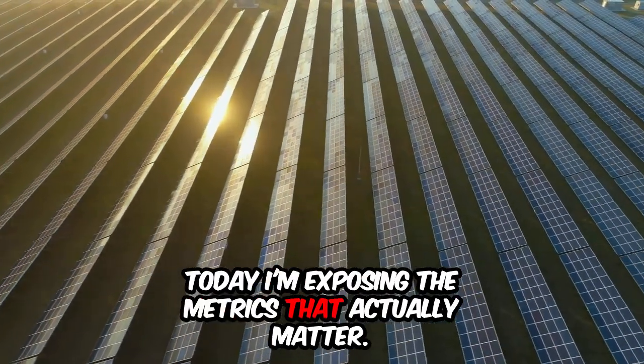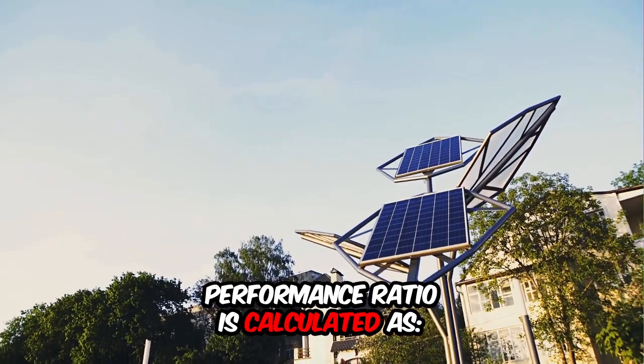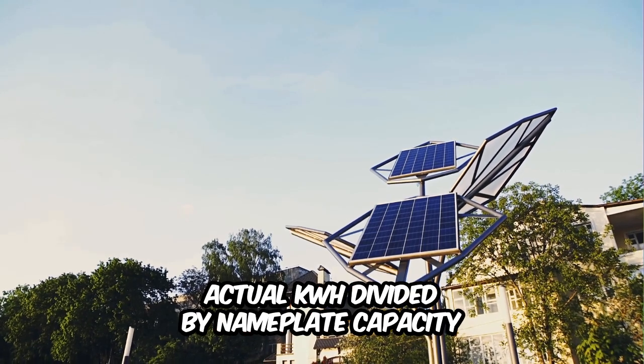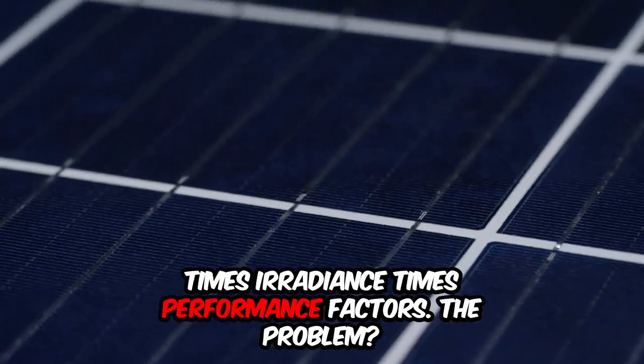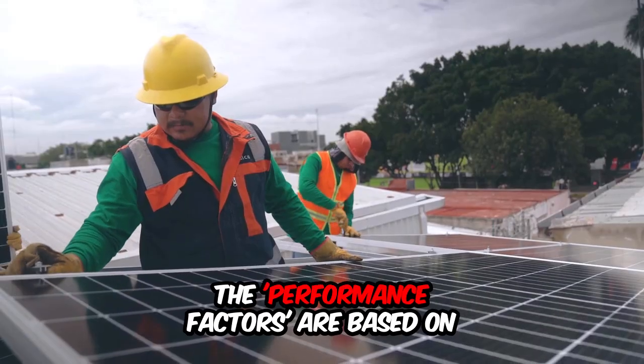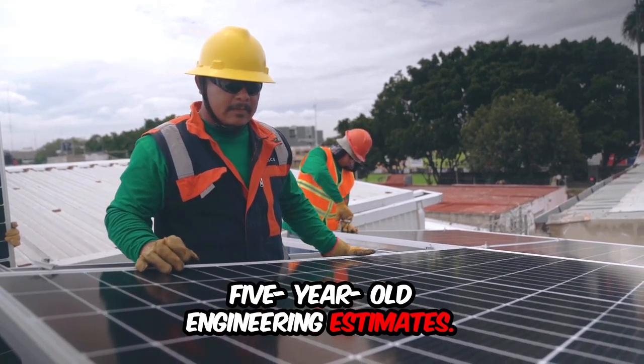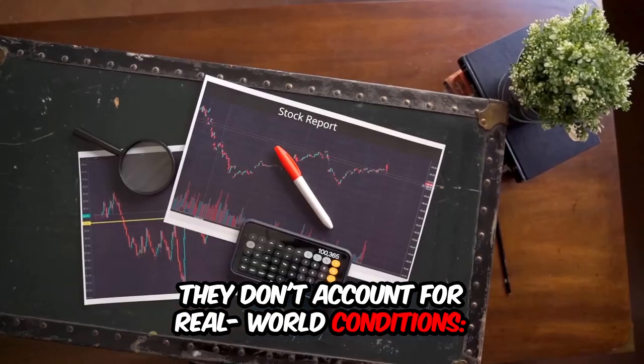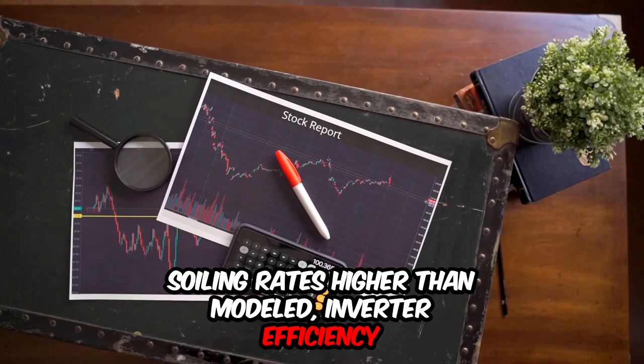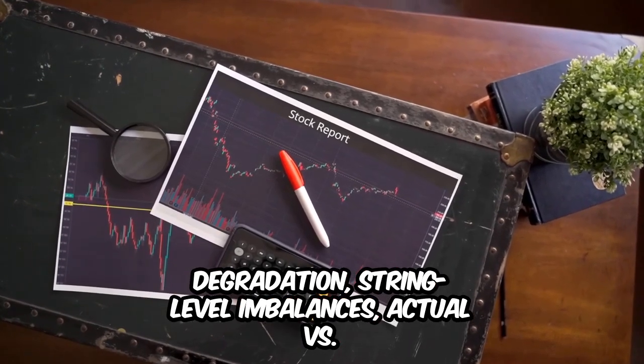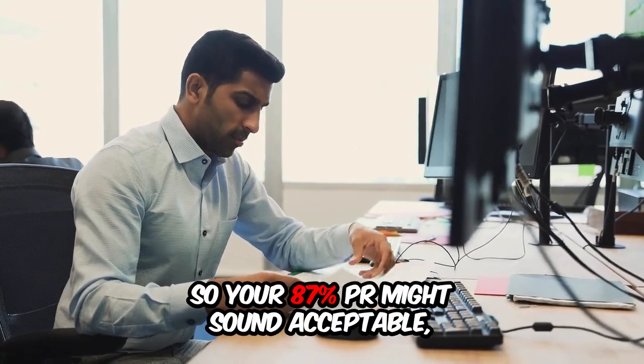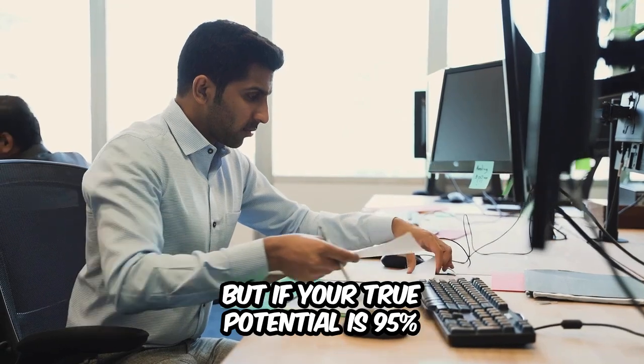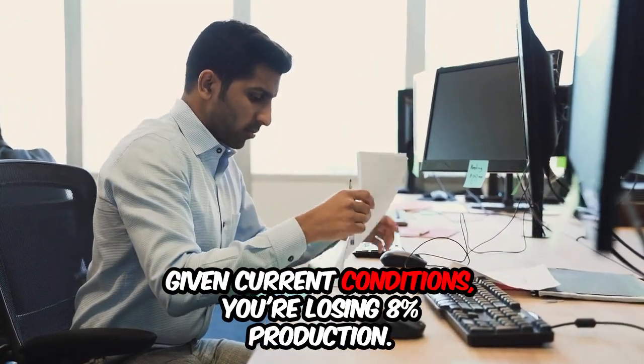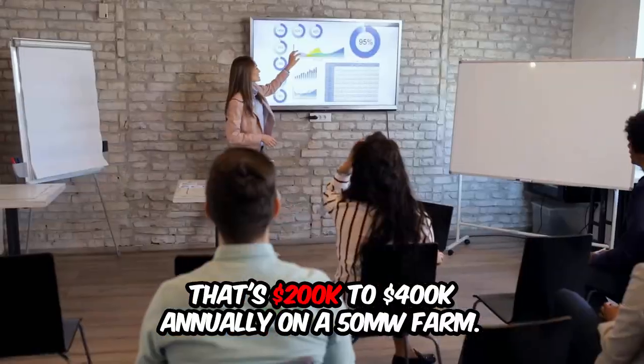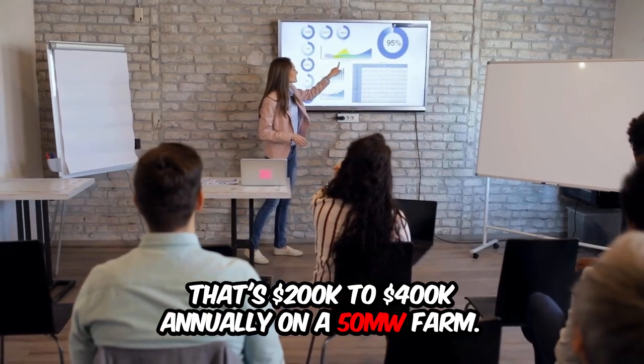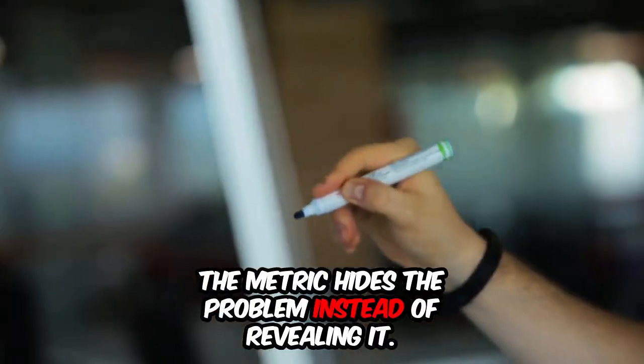Today, I'm exposing the metrics that actually matter. Performance ratio is calculated as actual kWh divided by nameplate capacity, times irradiance, times performance factors. The problem? The performance factors are based on 5-year-old engineering estimates. They don't account for real-world conditions. Soiling rates higher than modeled, inverter efficiency degradation, string level imbalances, actual versus modeled shading. So your 87% PR might sound acceptable, but if your true potential is 95% given current conditions, you're losing 8% production. That's 200K to 400K annually on a 50 MW farm. The metric hides the problem instead of revealing it.